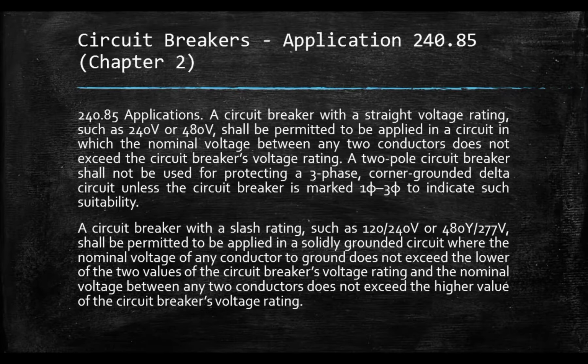240.85 Applications. A circuit breaker with a straight voltage rating such as 240 volts or 480 volts shall be permitted to be applied in a circuit in which the nominal voltage between any two conductors does not exceed the circuit breaker's voltage rating. A two-pole circuit breaker shall not be used for protecting a three-phase corner grounded delta circuit unless the circuit breaker is marked 1-phase to 3-phase to indicate such suitability.